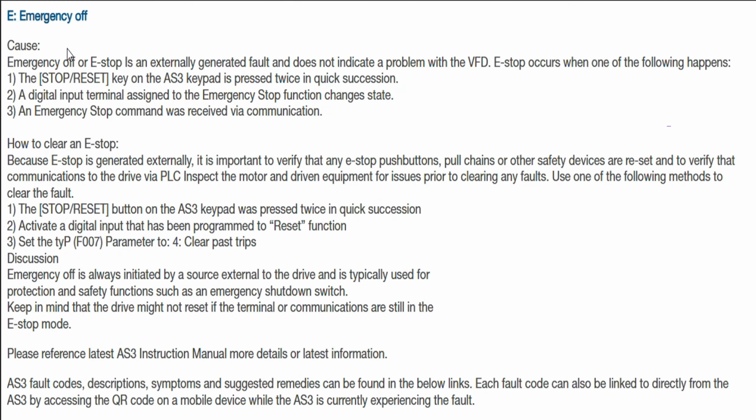Hello everyone, we will talk about Toshiba VFD fault. It's emergency off. This is not a fault of the VFD. Actually, this is about the external digital input, which is given for emergency stop, that is not coming properly.